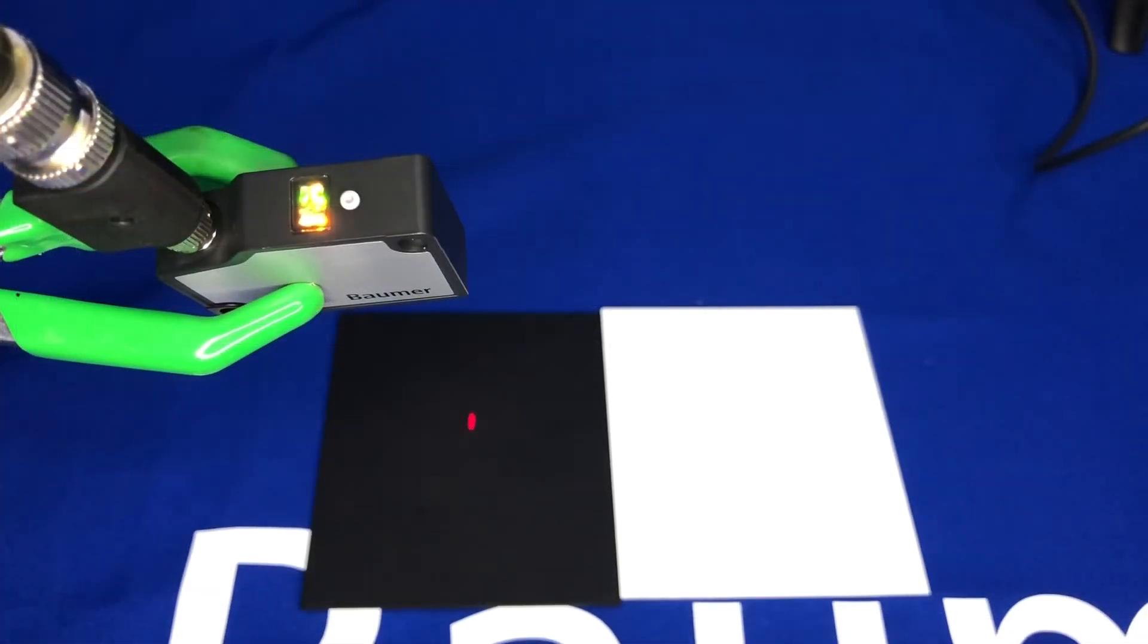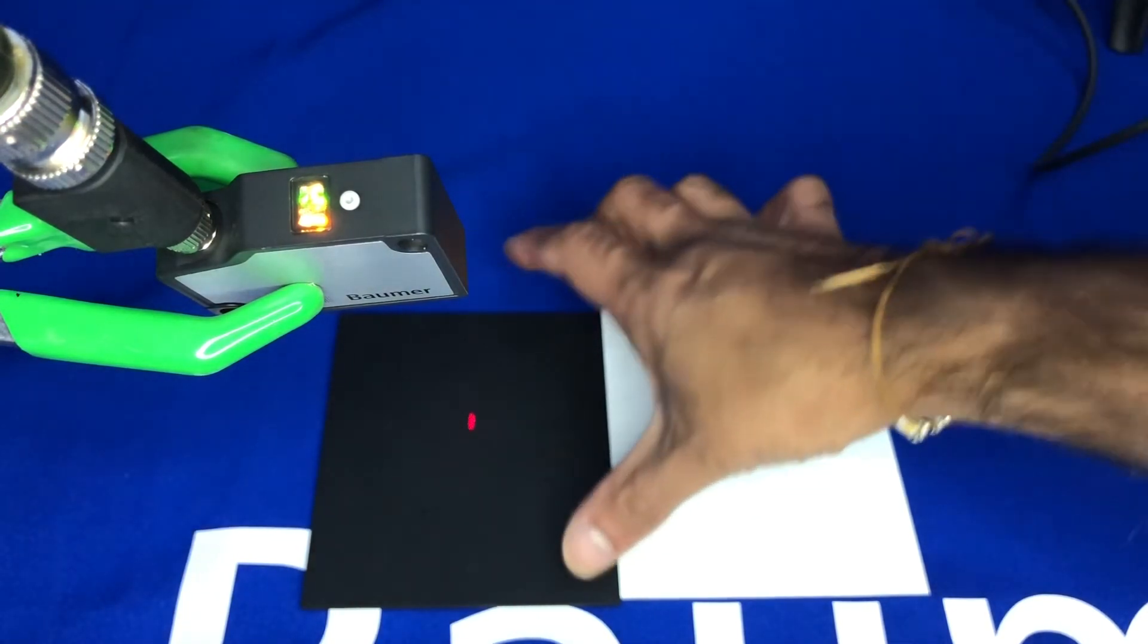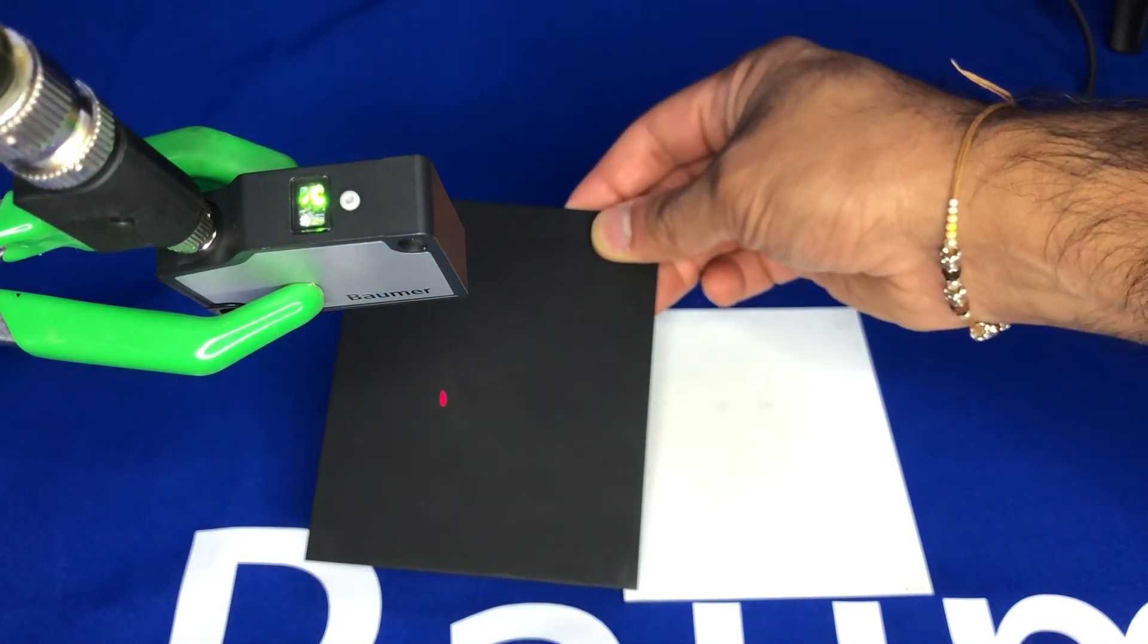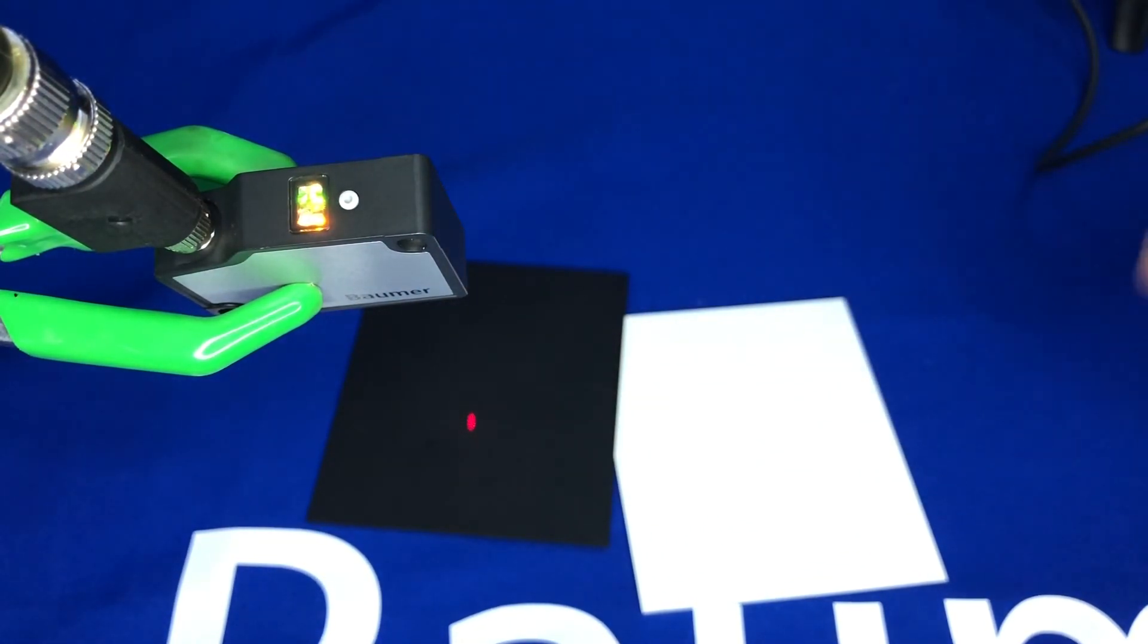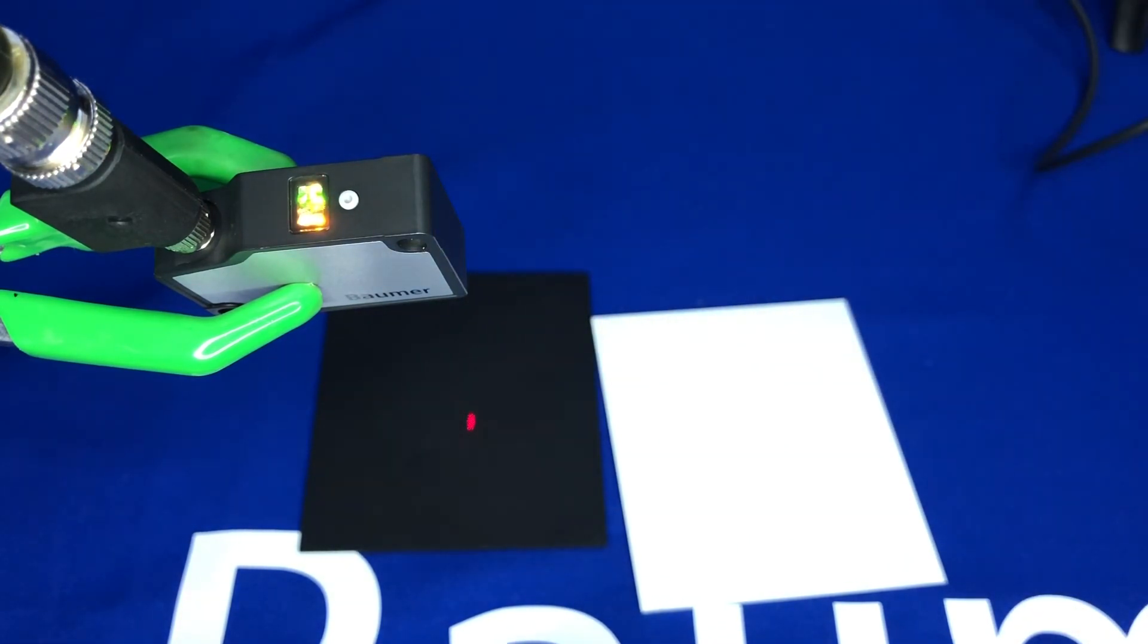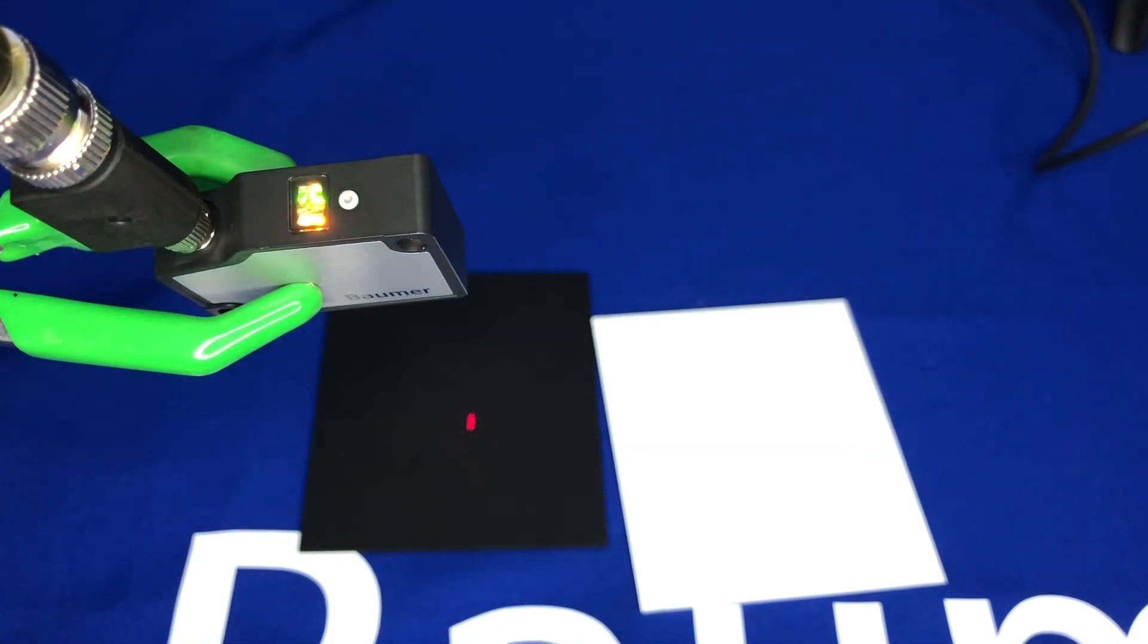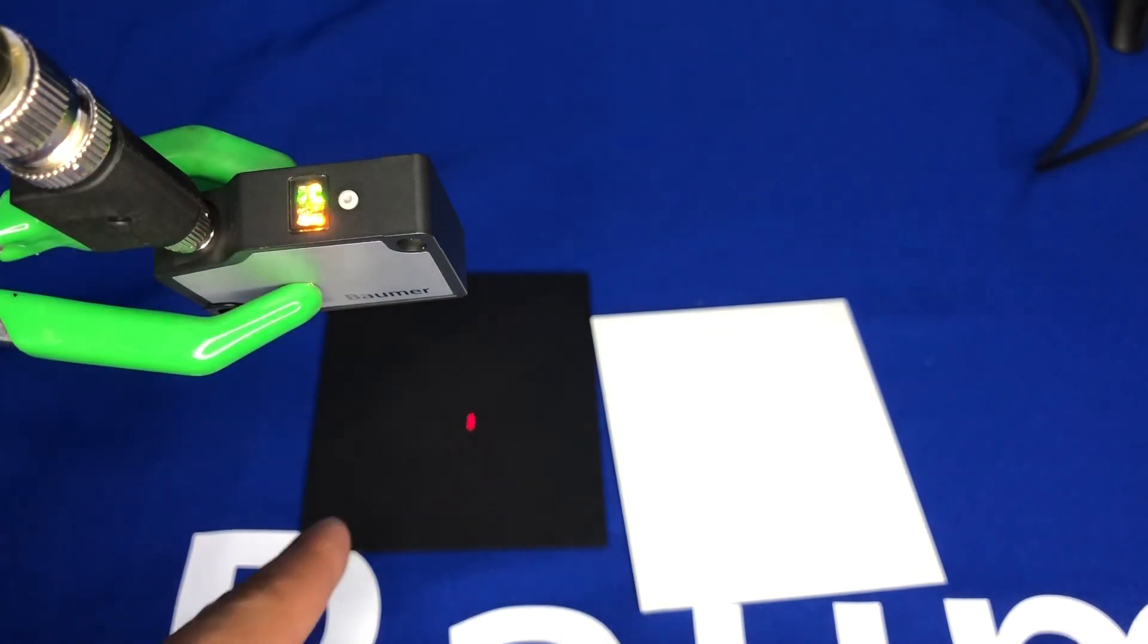You can see that the sensor was set up with a working range of 180 millimeters to 200 millimeters for its switched output, and we were at 183 millimeters. If I now bring this disc closer, you can see that the output goes off. Let me show you a bit clearer. And then back in, you see the output stays on. So it's on, off, on, off. Via the IO-Link settings we switched the capability of the switching point of the sensor from alarm to a physical distance switch to turn on and off at a single point or between a range, a window so to speak. I set the window between 180 and 200 millimeters as okay and no good outside of that. So the output's on here now because we're at 183 millimeters. I bring something closer, the output turns off.